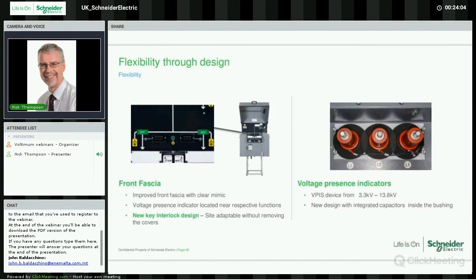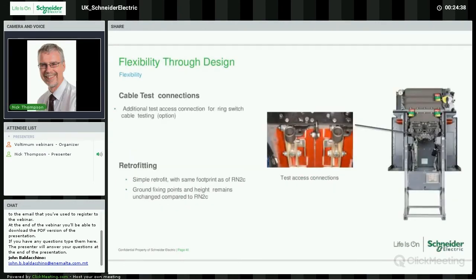With voltage presence indicators, they are now mounted on the front fascia rather than inside the drop-down LV box, and they are connected to the screen that's buried or cast into the bushing. This is a much more reliable device over and above the RN2C, which has a garter spring which goes around the bushing, and the VPIS now is one device that goes from 3.3 kV up to 13.8 kV. The VPIS is one of the options. Not everybody wants it, but it's very useful when it's used.